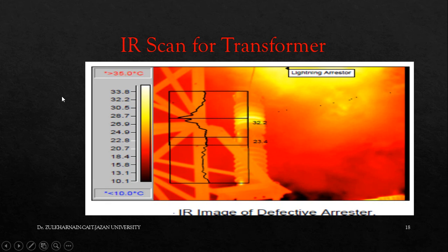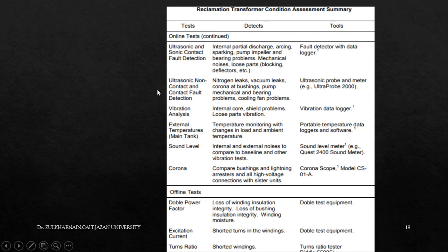Similarly, to measure the temperature, we use an IR scan, infrared scan. So just point the IR scanner directly at the transformer. It will show you how much temperature, minimum to maximum possible. So if at all you have a problem in the transformer, you need to have different tests done. Okay, so like ultrasonic test, this is for arcing, sparking, and pump impeller check, so you can detect the fault.